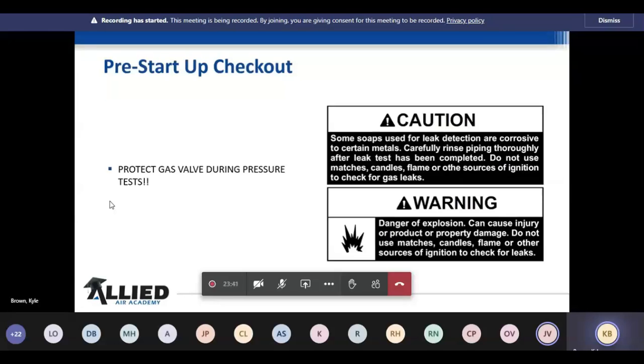If you have multiple units on a rooftop and you do your gas pressure check before you even crank the units up, and they run the gas lines, and the units are sitting there, if you don't have a gas cock between the unit and the regulator and you put 1 or 2 psi on that gas valve, it is no longer any good. So we have to make sure, whatever the code calls for, you need to protect the gas valve during that.